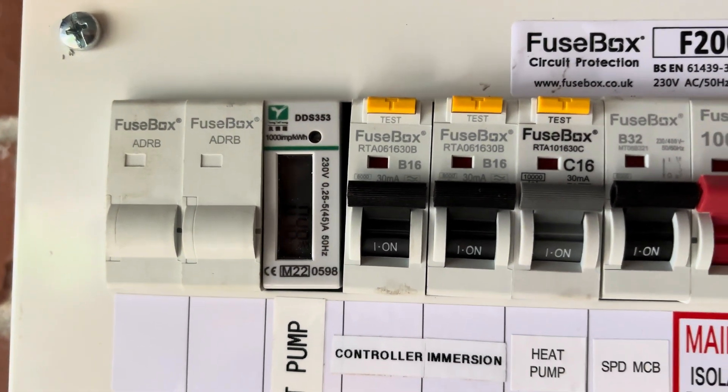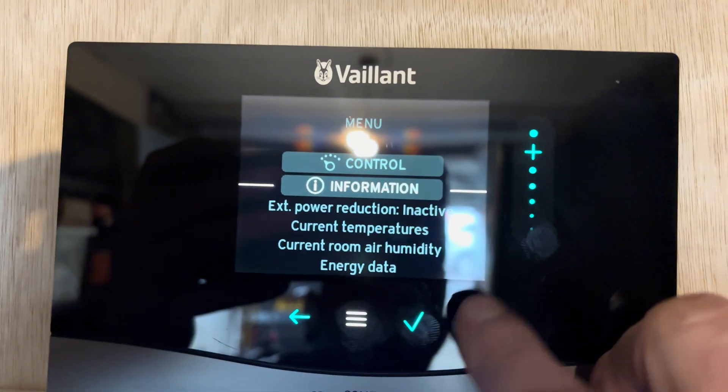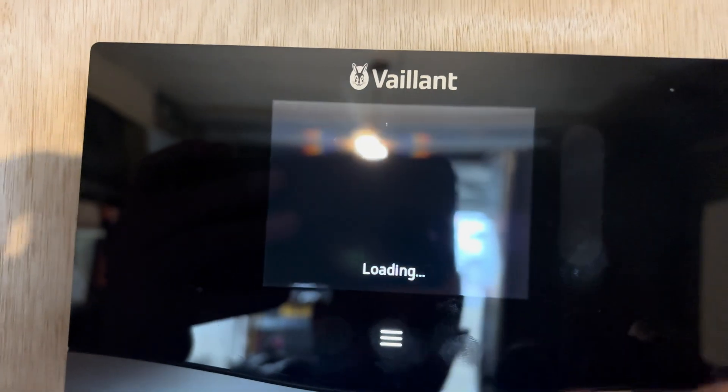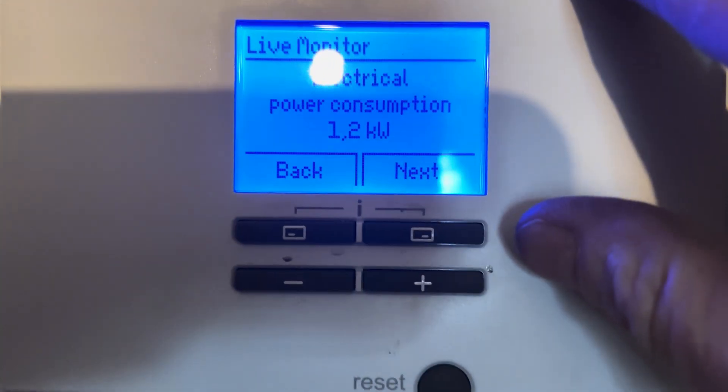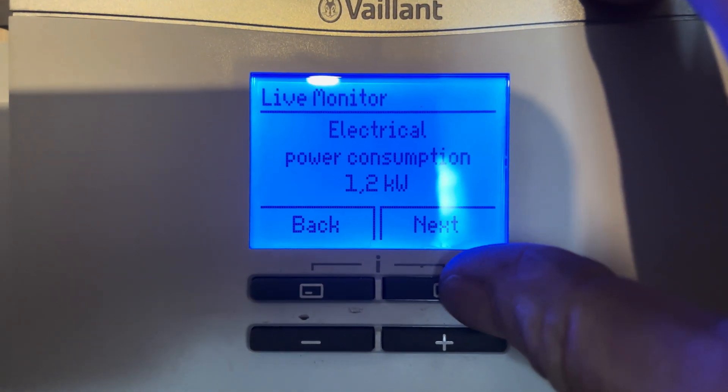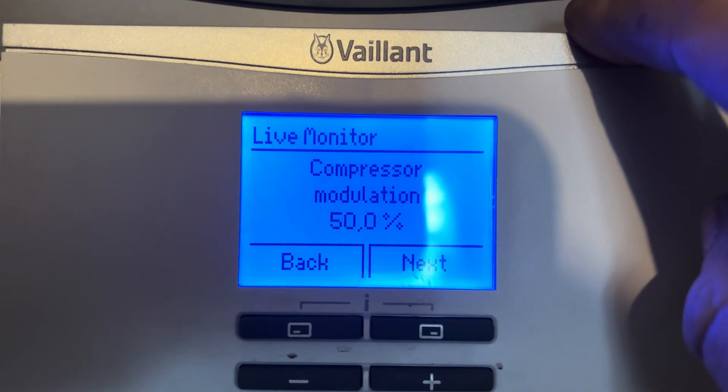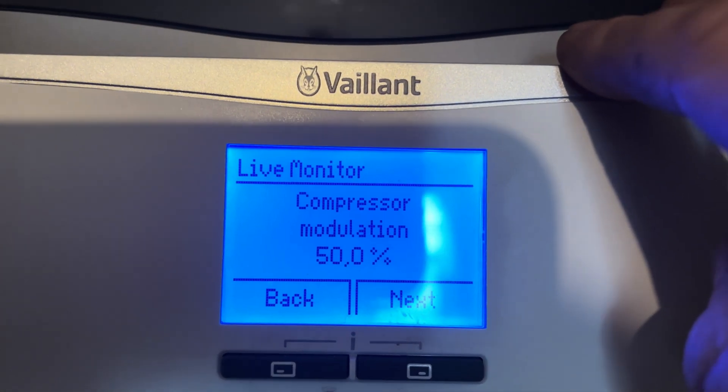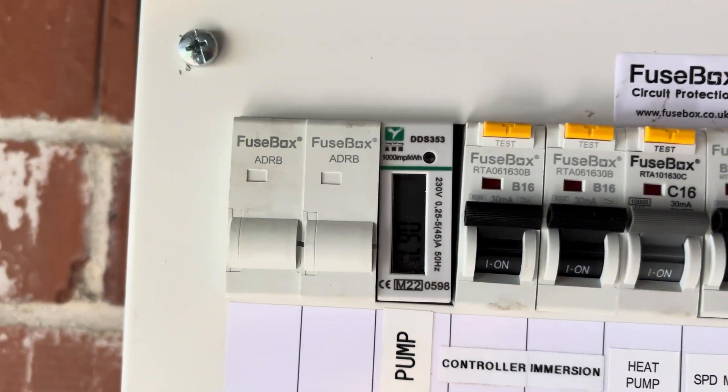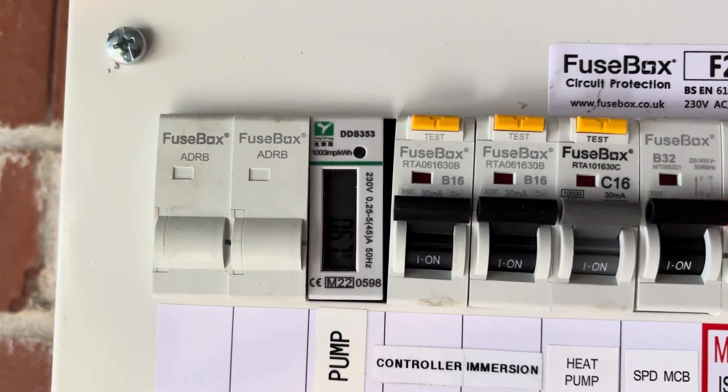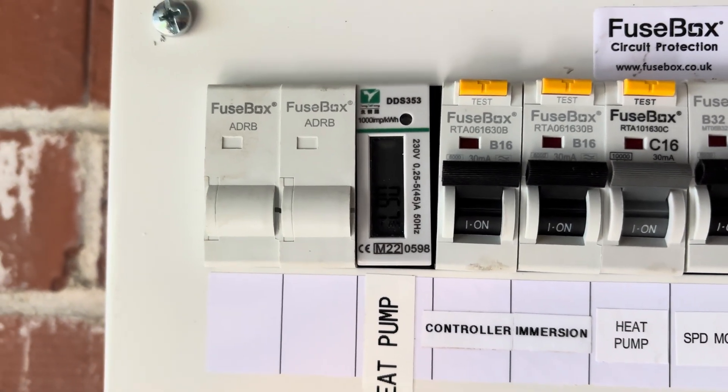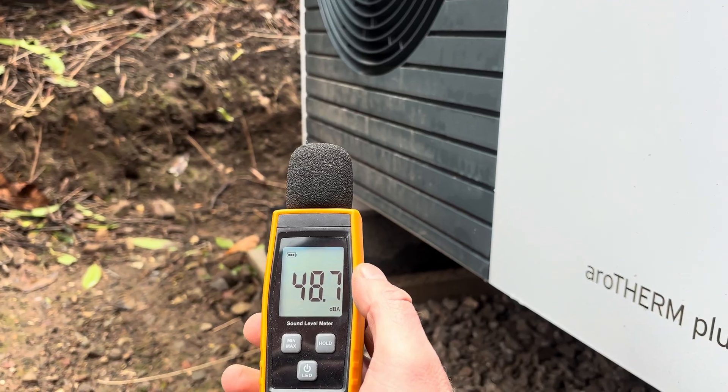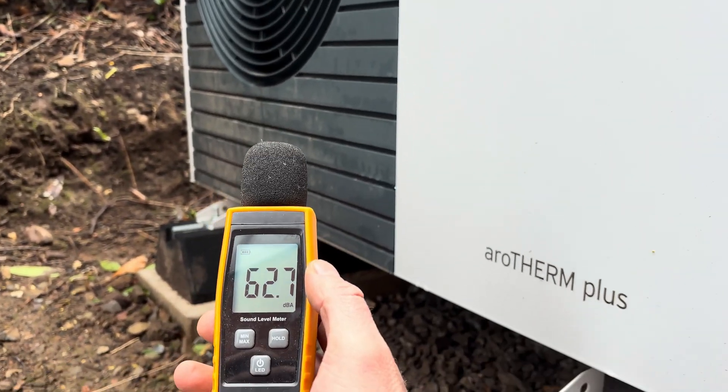40 minutes in now. So our hot water temperature is now at 23 degrees C from 11. Power consumption, 1.2 kilowatts. Modulation is still 50%. Over at the electric meter now we are at 0.67 kilowatts. So 670 watts so far. And as we can see, she's still nice and quiet.